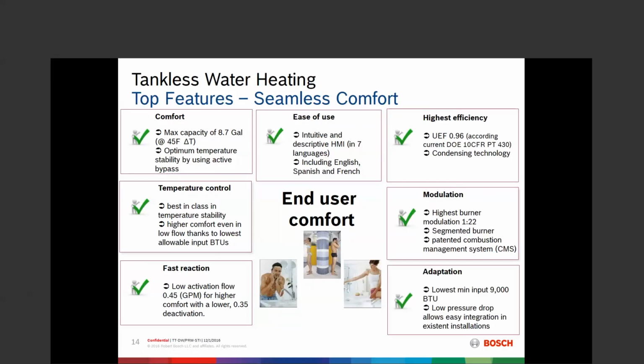Very low pressure drop, and when we talk about pressure drop, we can talk about the pressure drop through the heat exchangers themselves, how much water pressure drop is there on this unit. But we also find it's very important to talk about pressure drop through the combustion chamber and how hard the fan has to work to push the exhaust. So we actually have a very low pressure drop there, which is what allows us to go out to that 60-foot equivalency on 2-inch PVC.